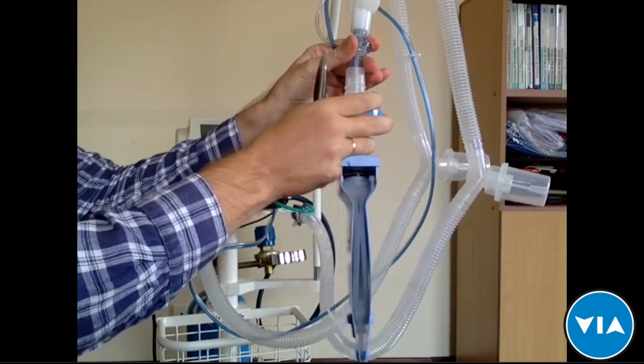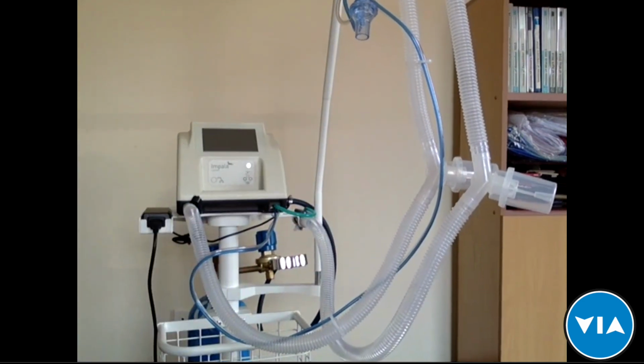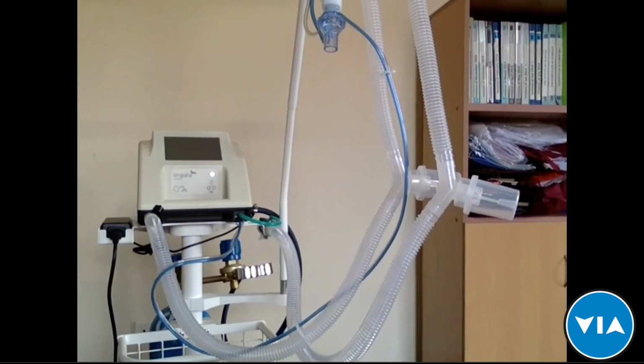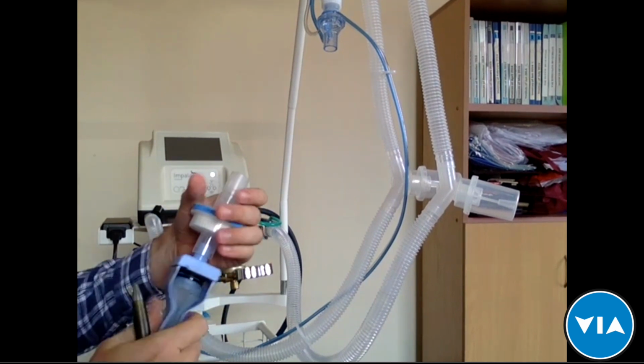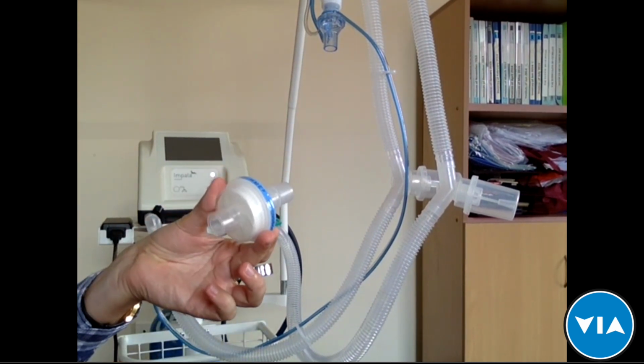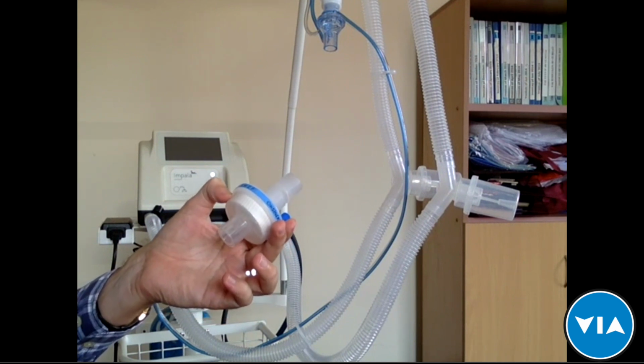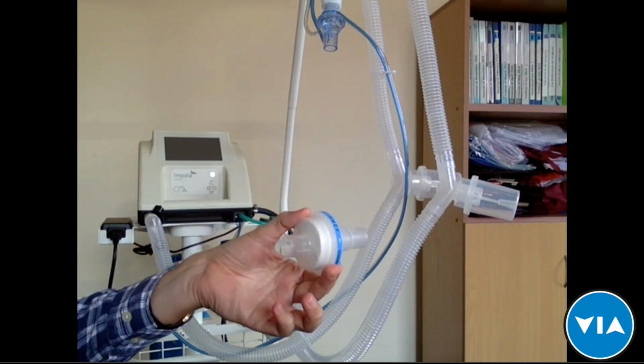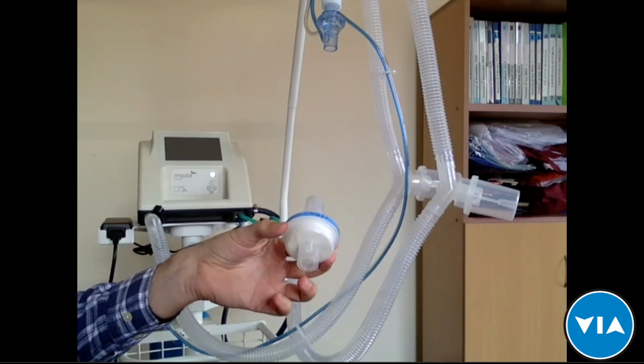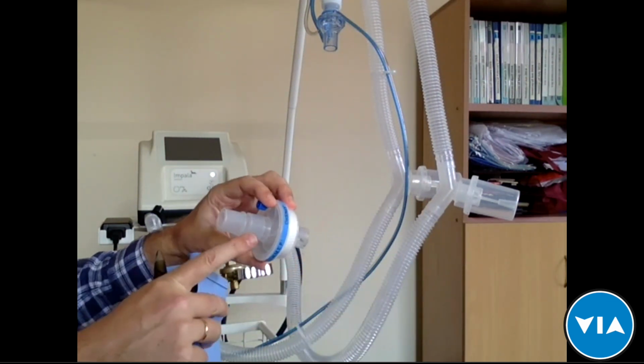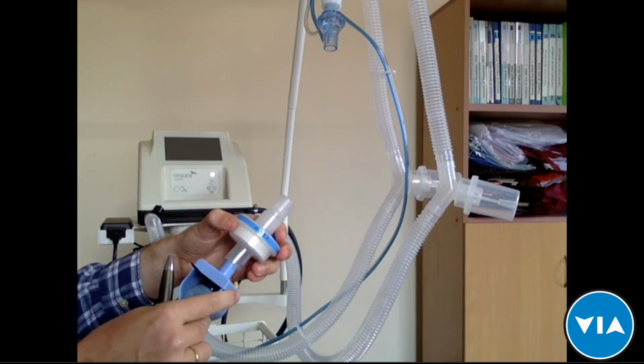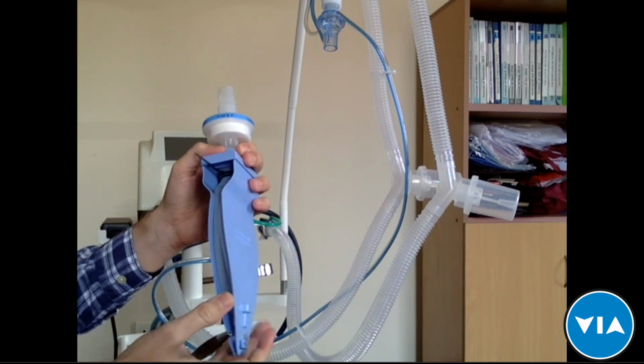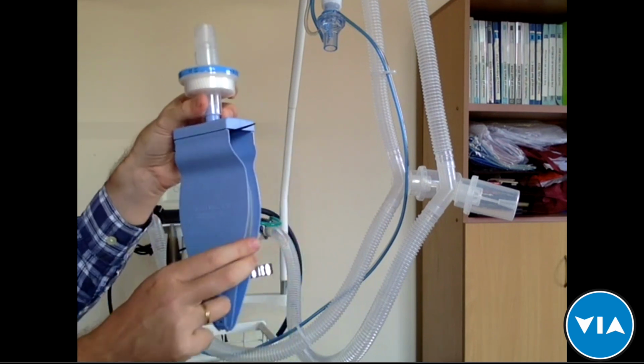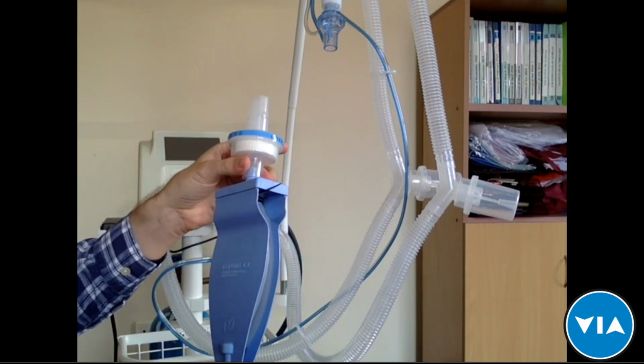We also offer this entire breathing circuit as reusable, cleaned and disinfected, with the exception of this part, which is called the HMEF filter, heat moisture exchange filter. This part unfortunately has to be disposed. It's not possible to clean because it's a filter, not possible to autoclave or disinfect. The lungs here are optional. These are for testing.